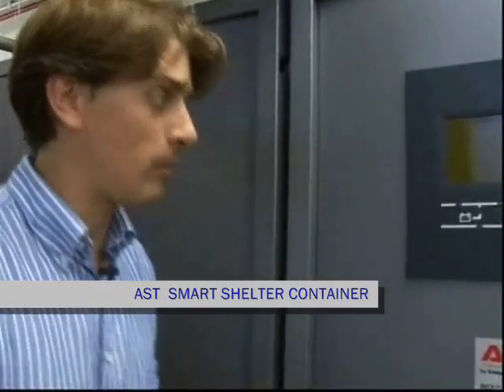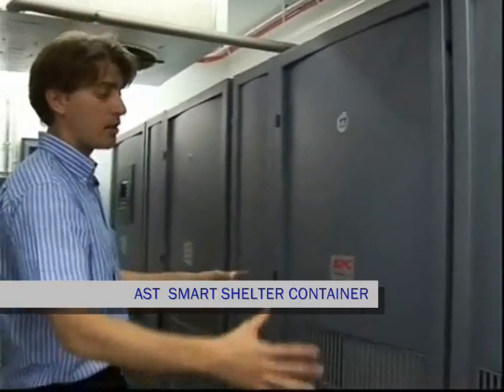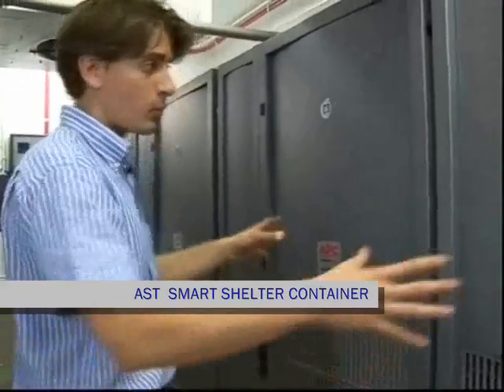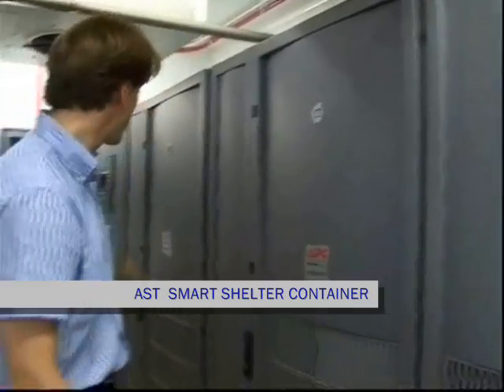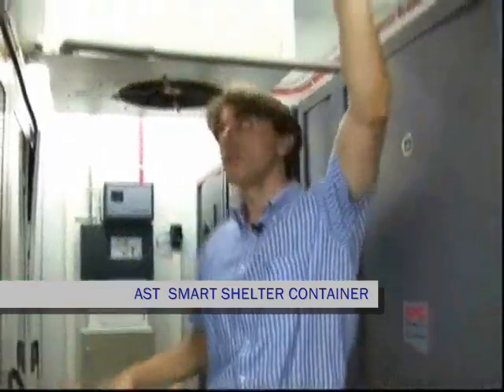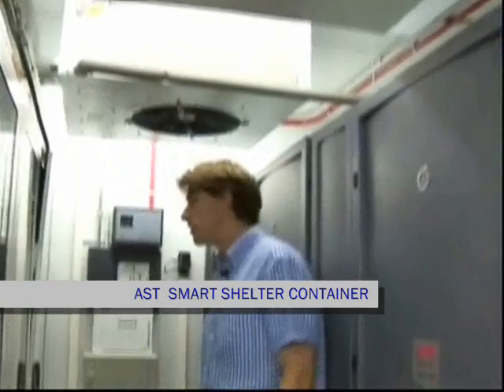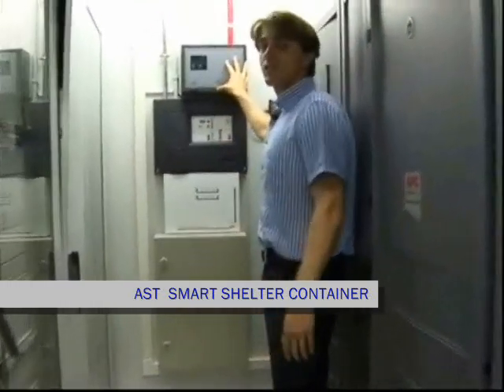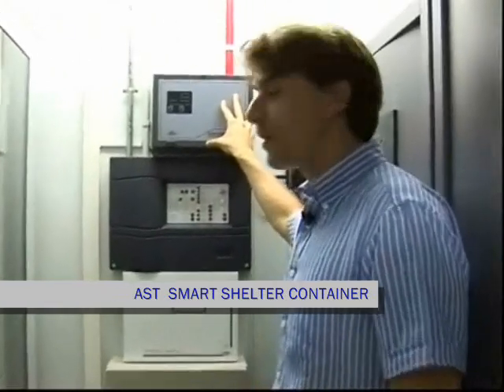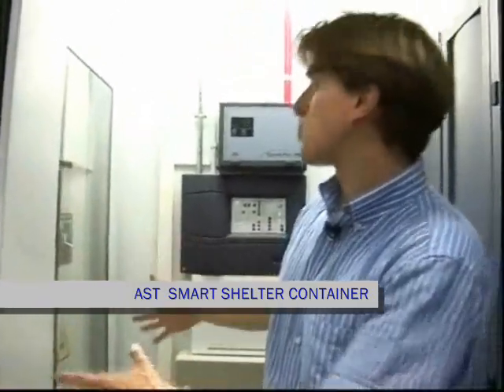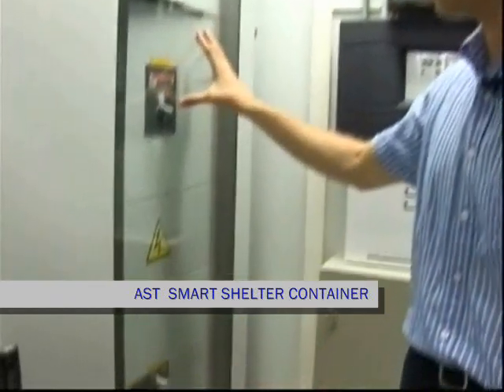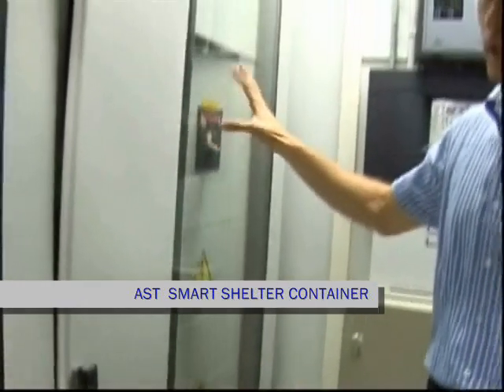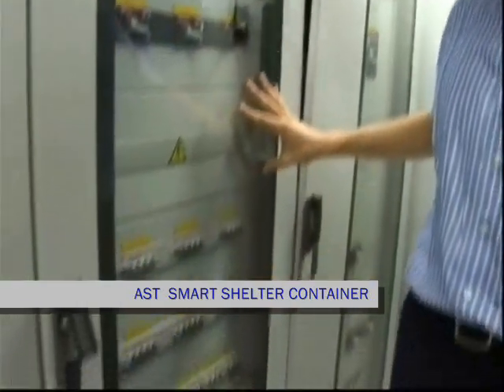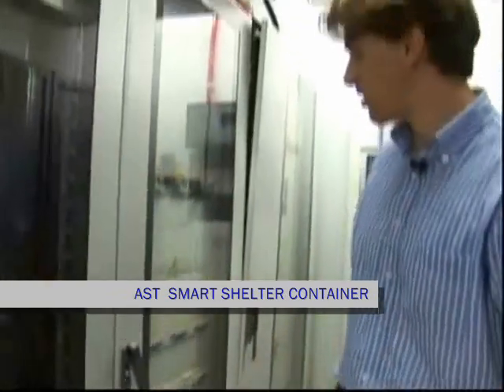There are different technologies that we can assemble in order to provide higher density, as I was explaining before. If we move into the services area, we see here a totally 2N redundant unit in which we have assembled two UPSs, 100 kVA each, in a redundant configuration, together with redundant air conditioning to provide enough cooling in this area. Early detection systems as well, to provide appropriate security from fire and internal fire hazards, together with the switchboards. Main breaker for the main feeding, together with an ATS for the genset. Then we go into the switchboard where we protect all our services units, such as air conditioning and UPS.